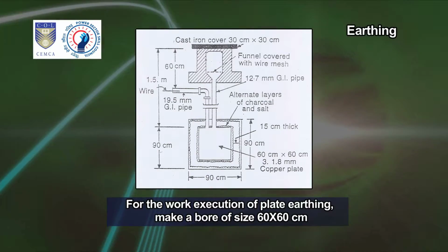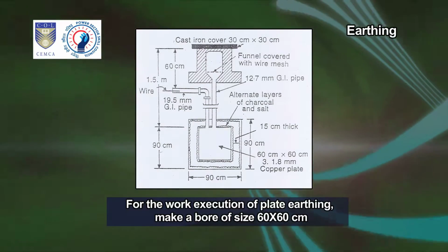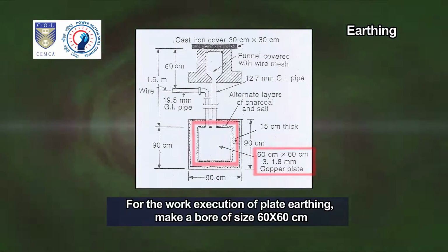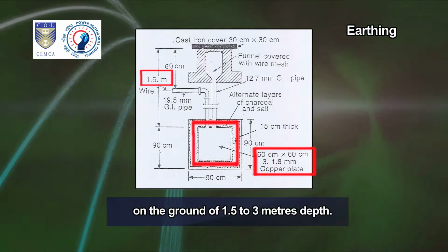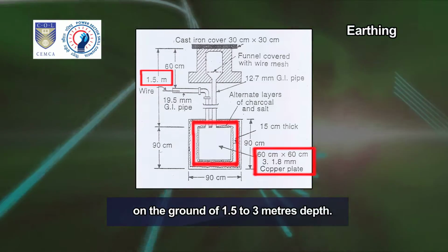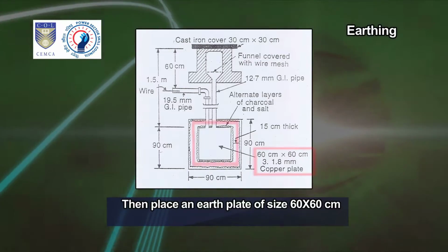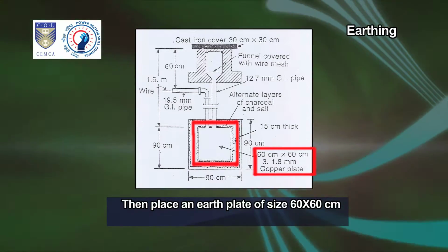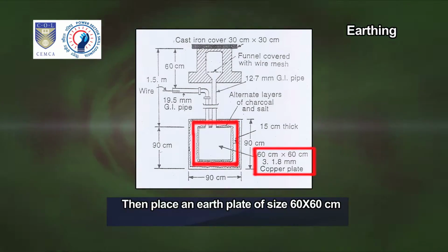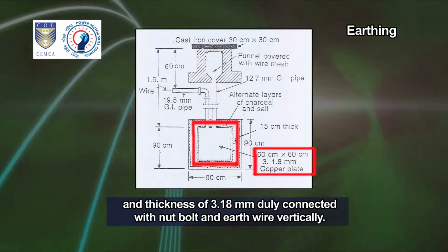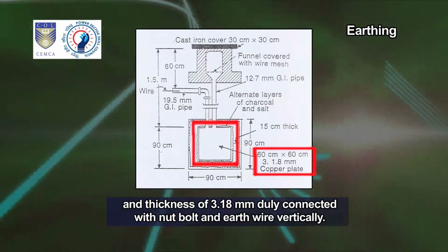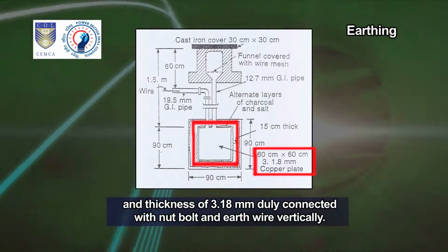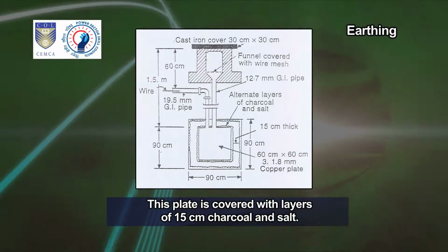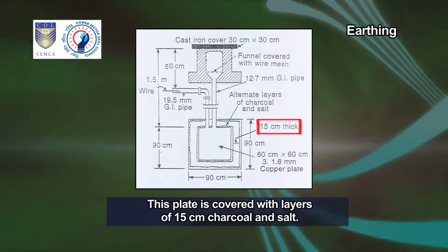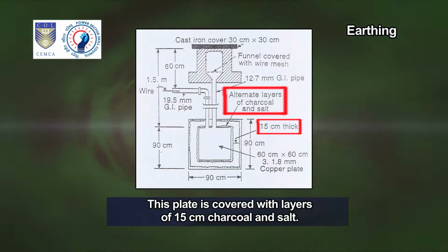For the work execution of plate earthing, make a bore of size 60 by 60 centimeters on the ground, 1.5 to 3 meters deep. Then, place an earth plate of size 60 by 60 centimeters and thickness of 3.18 mm, duly connected with nut, bolt and earth wire vertically. This plate is covered with layers of 15 centimeters of charcoal and salt.